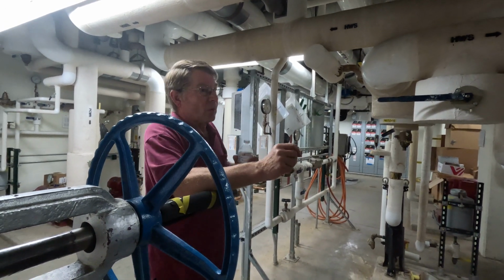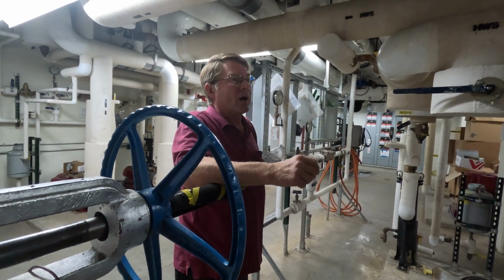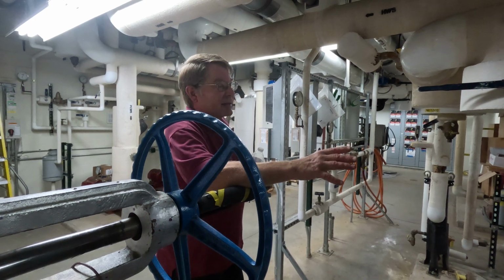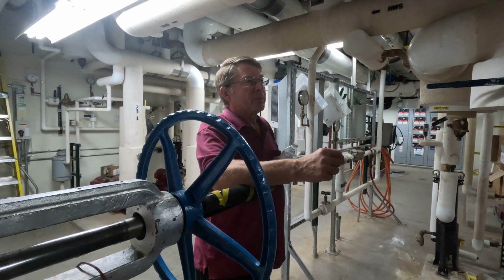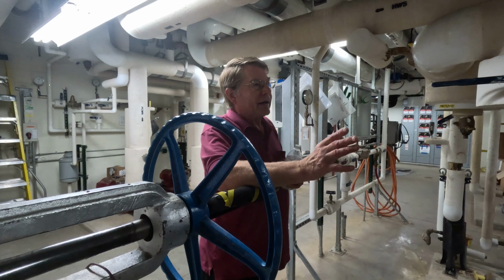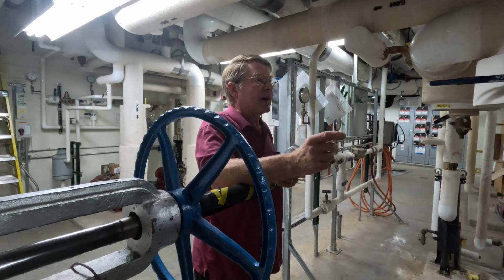And then the central chilled water comes in at the same spot, comes across. We do have two central chilled water pumps here. The central chilled water is for cooling. It's got to go all the way to the penthouse, which is up on the 6th floor. Campus has some very large pumps that you'll see that actually keep this moving. The problem is that we have a capacity issue. If there's a leak in the system or a failure, our pump will automatically turn on to keep the system moving so that we get chilled water all the way up to the top of our penthouse.